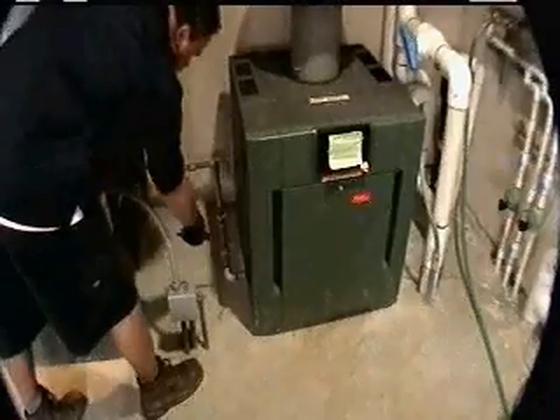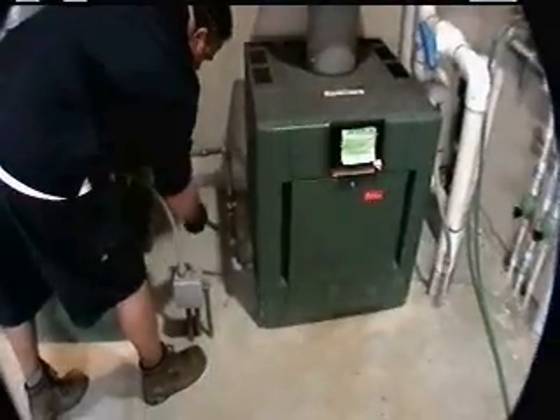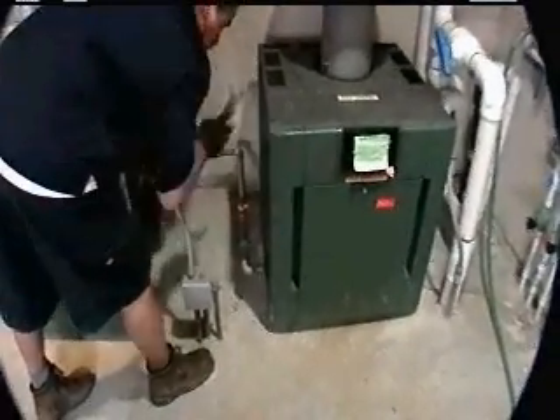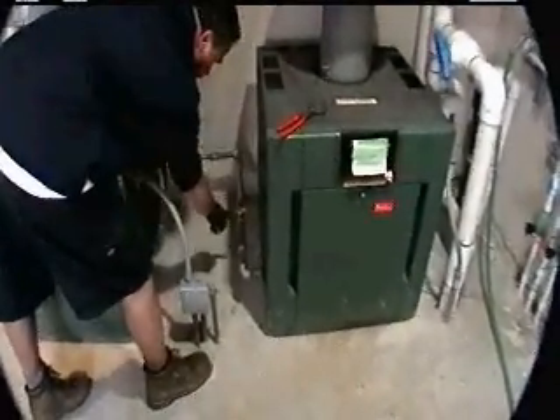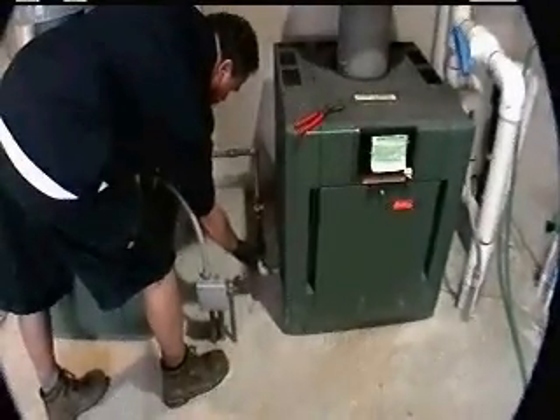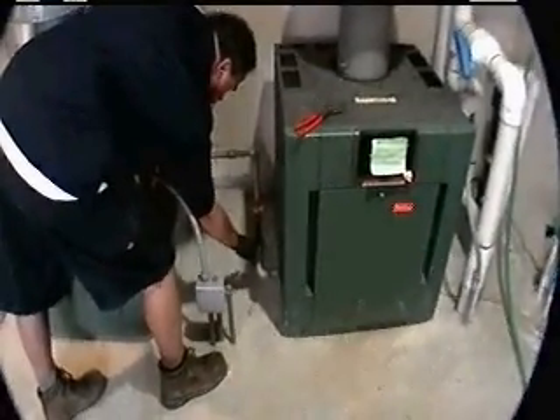So this particular heater, we had determined in our annual heater inspection that the heat exchanger was sooting up, and that the cause of that was calcified tubes, and this was also reducing the efficiency of the heater. You can see there still is some evidence there of the heater sooting.